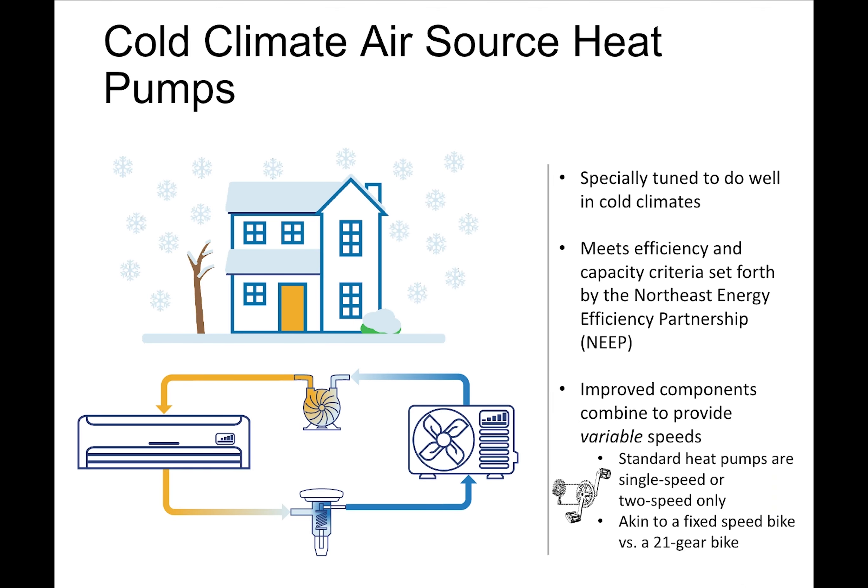The cold climate air source heat pump is considered to be products listed on the US EPA's Energy Star website list of qualified cold climate air source heat pumps. Cold climate heat pumps have multiple operating speeds that fine-tune their operation to match heating and cooling loads to outdoor ambient conditions. The enhanced capabilities allow improved heating performance on the coldest days and extend cooling performance on the hottest days. The solid state controls use algorithms to adjust the speed of the compressor, fans, and the position of the electronic expansion valve to minimize ramping up or down to meet load conditions.